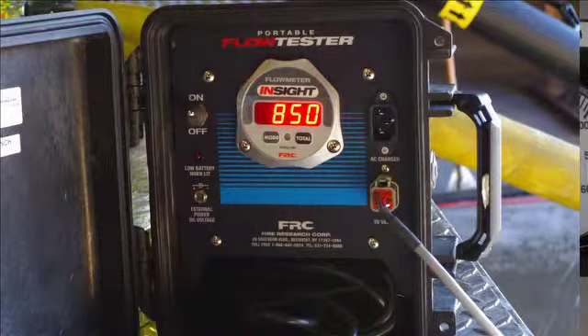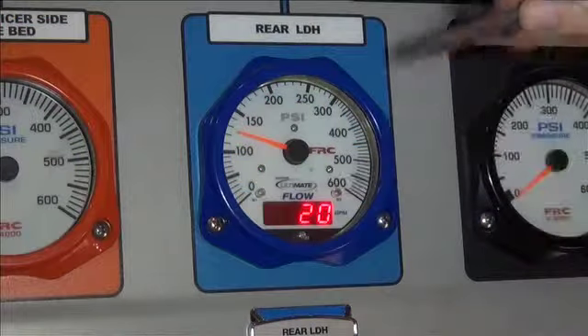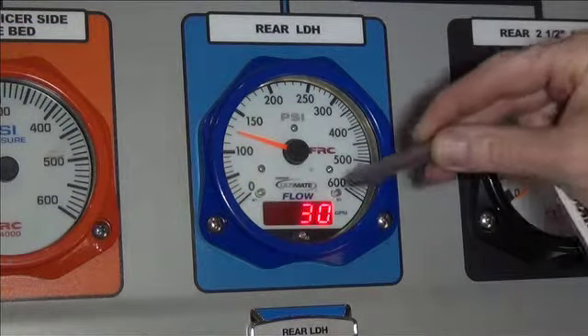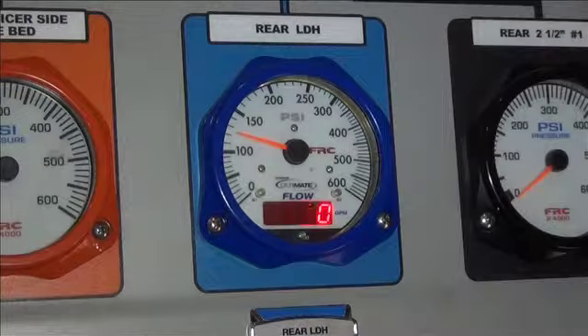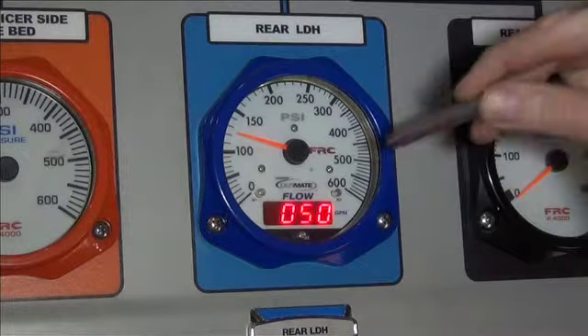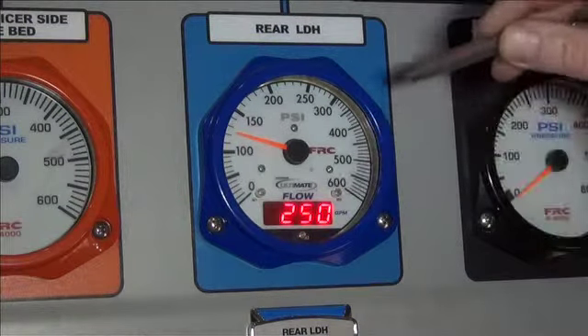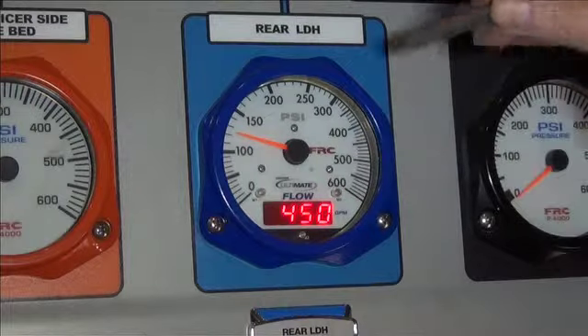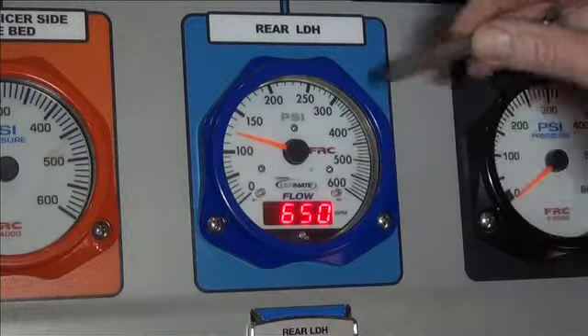These calibration points should be in the most commonly used range of the discharge. Each point must be at least 5% different from any other calibration point. In this example, we will finish the calibration process after calibrating 5 points.